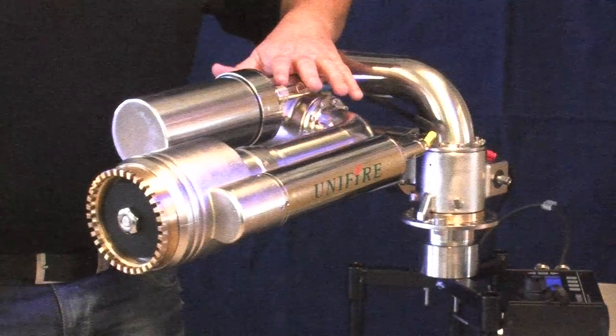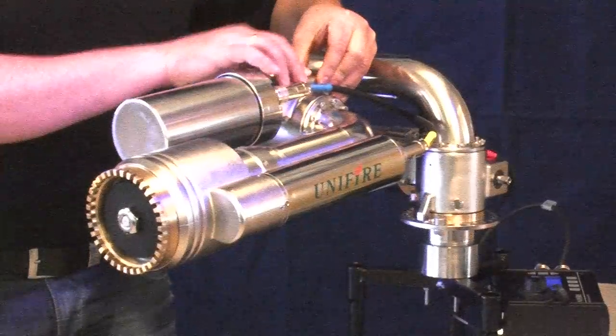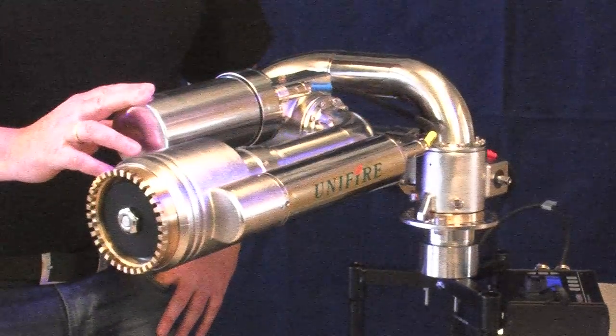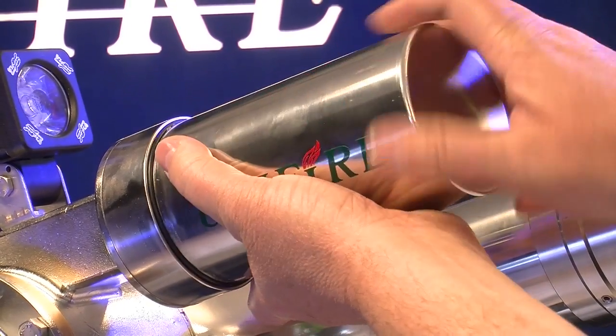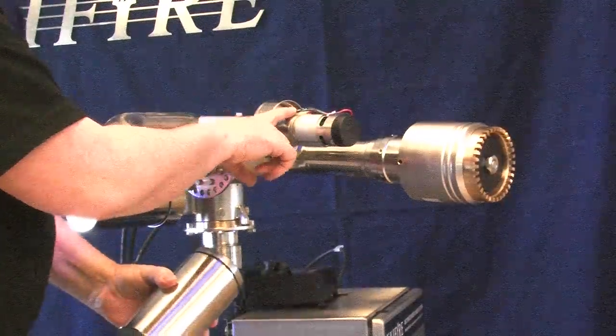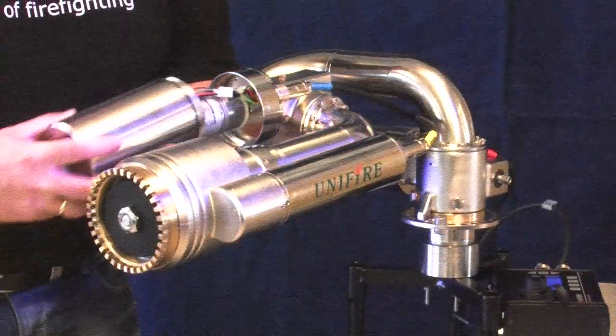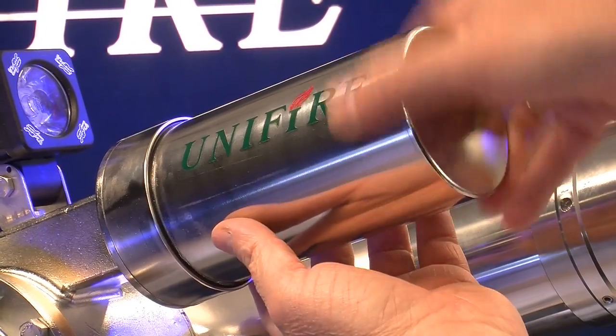The Unifire Force Monitors are controlled directionally by gears integrated in a cast stainless steel enclosure, driven by electric motors located in the stainless steel canisters. It's very simple to inspect the motors — just untwist the canister, open it up, and inspect to make sure everything is clean and dry. Changing the motors is fairly simple, taking only minutes, as they are connected by multi-connectors. To replace, just put the canister back on, twist it, and you're done.